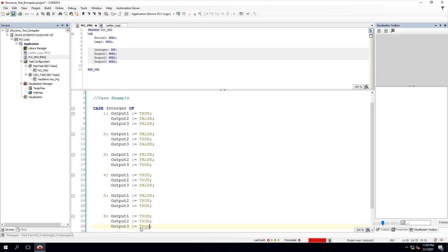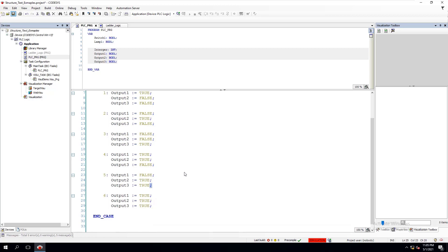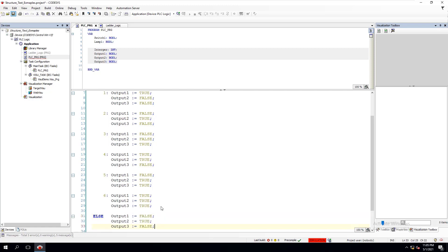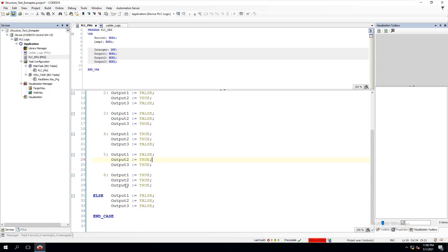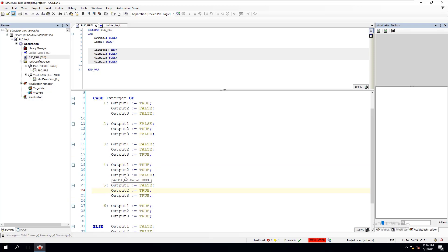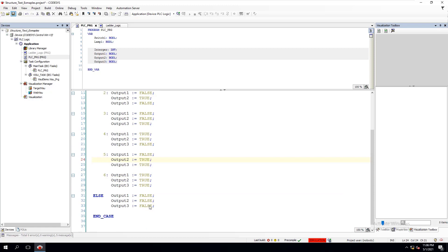We're doing cases one through six. On the counter side to that, we're going to do an ELSE. We'll do the ELSE and set all outputs to FALSE — so we'll cut all of these off. The reason we're doing the ELSE: if the integer is NOT between one and six, then we want to turn all outputs off.